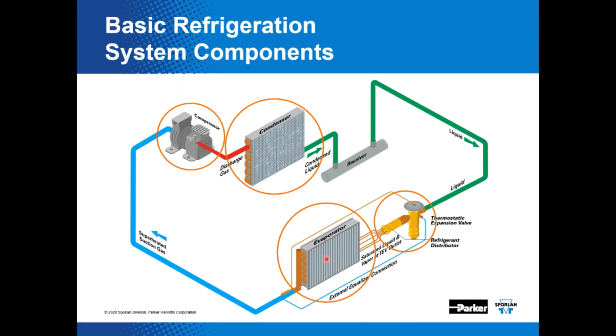Here's the evaporator. Refrigerant absorbs heat from the refrigerated space, and the refrigerant boils and changes phase. It should be 100% vapor as it leaves the outlet so that we don't cause a problem at the inlet of the compressor, and everything continues on and over again.